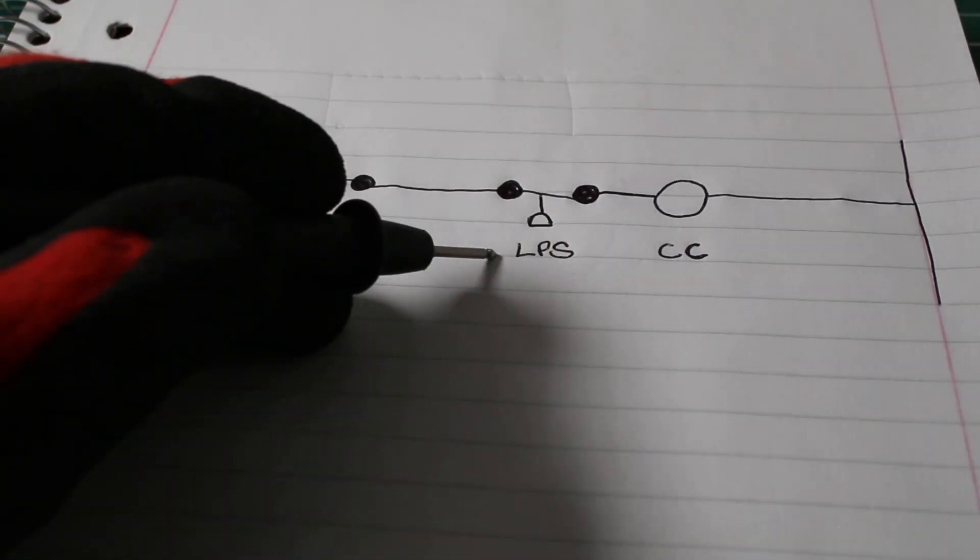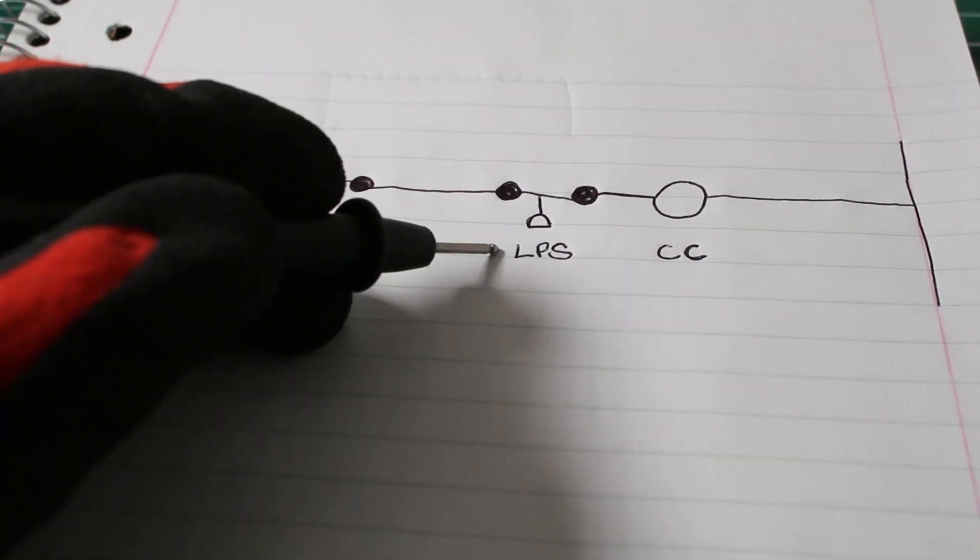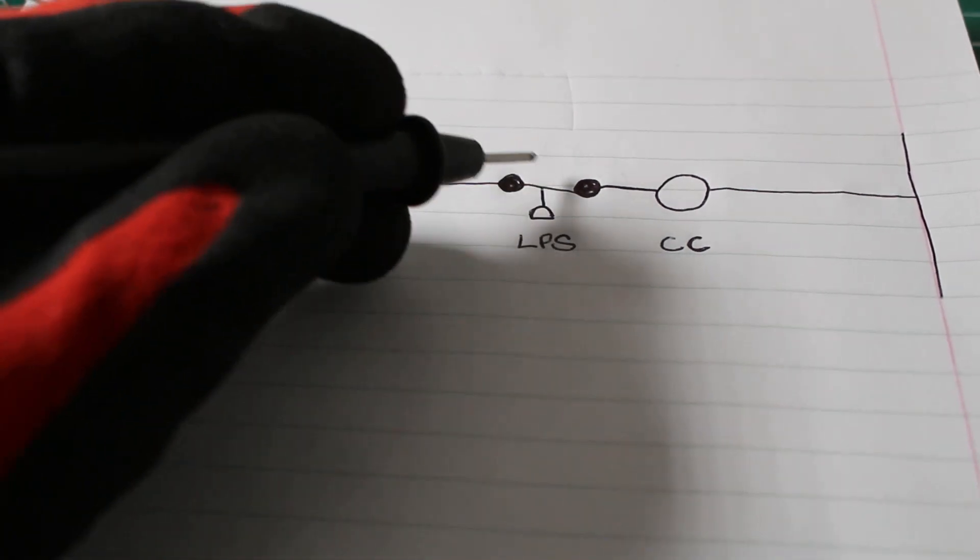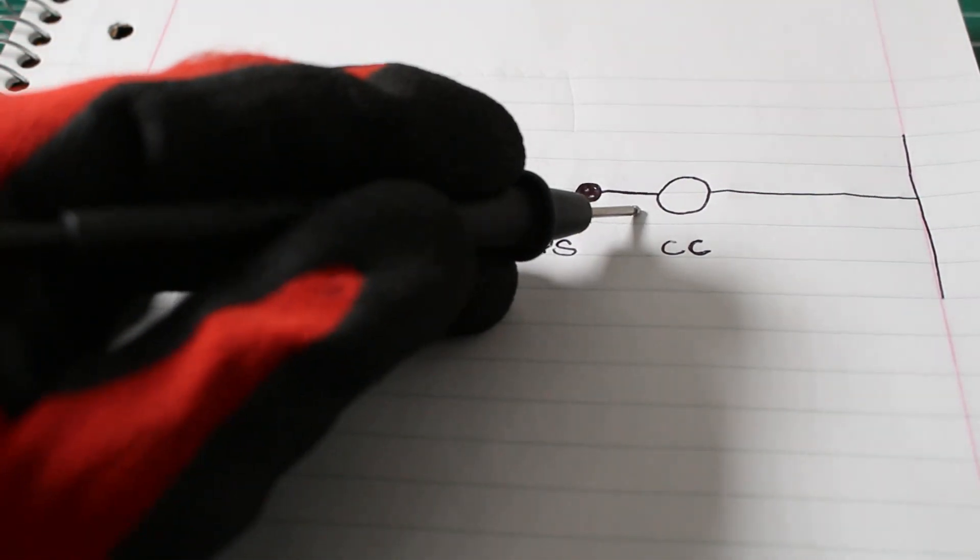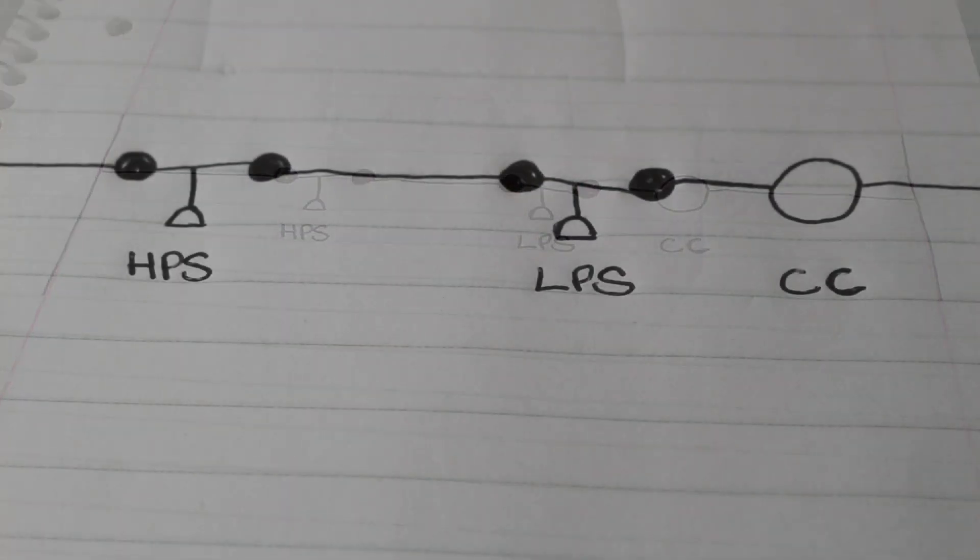Same thing for the low pressure switch, except if we have a low pressure situation. This switch will open and stop the power going to our coil, so we cannot complete our circuit and shut our equipment down. Pressure controls operate with the principle same as a switch and they are NC, which stands for normally closed.